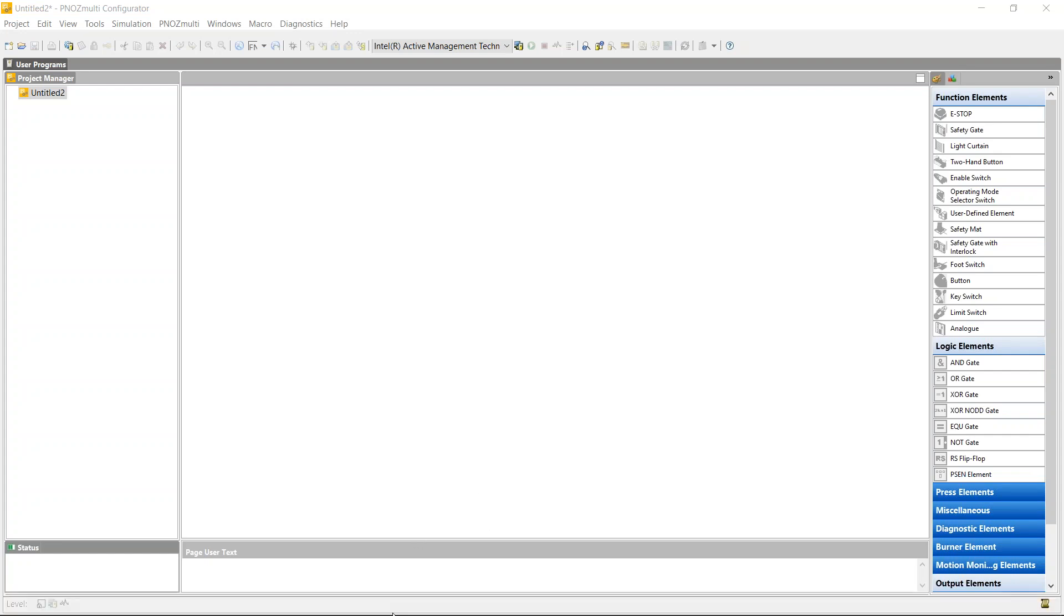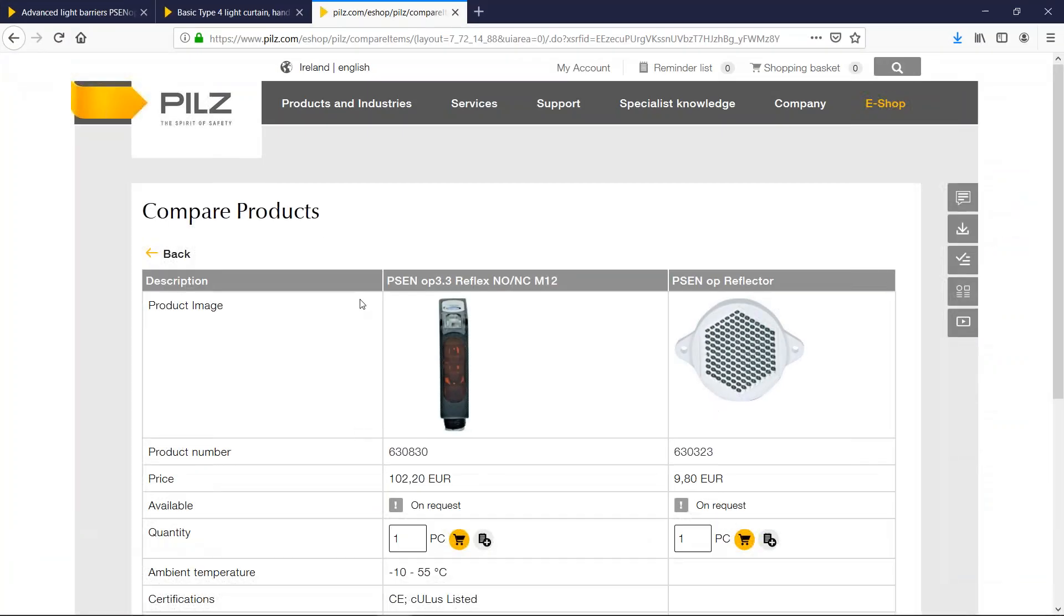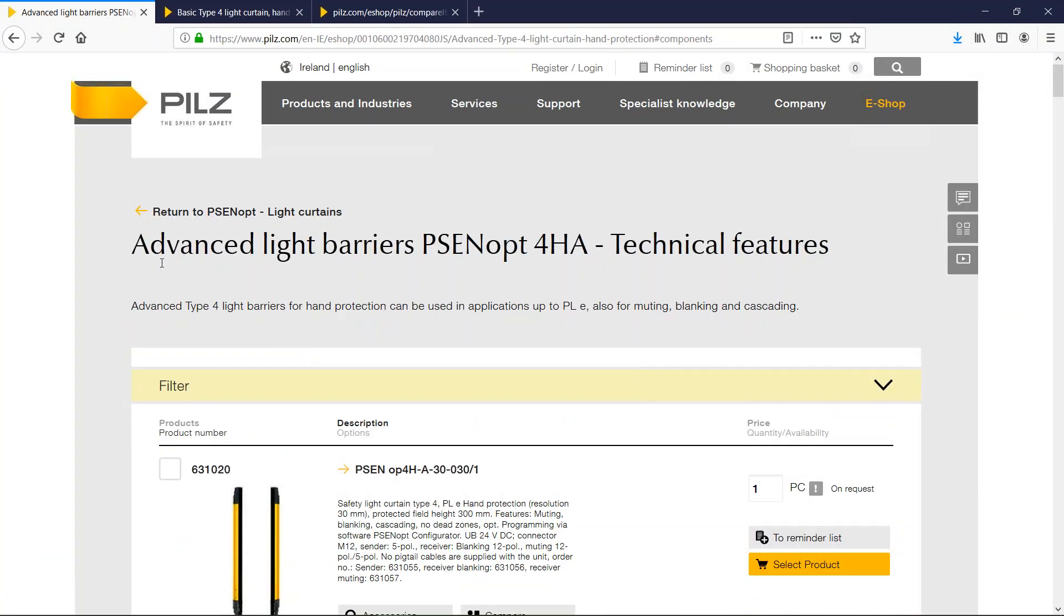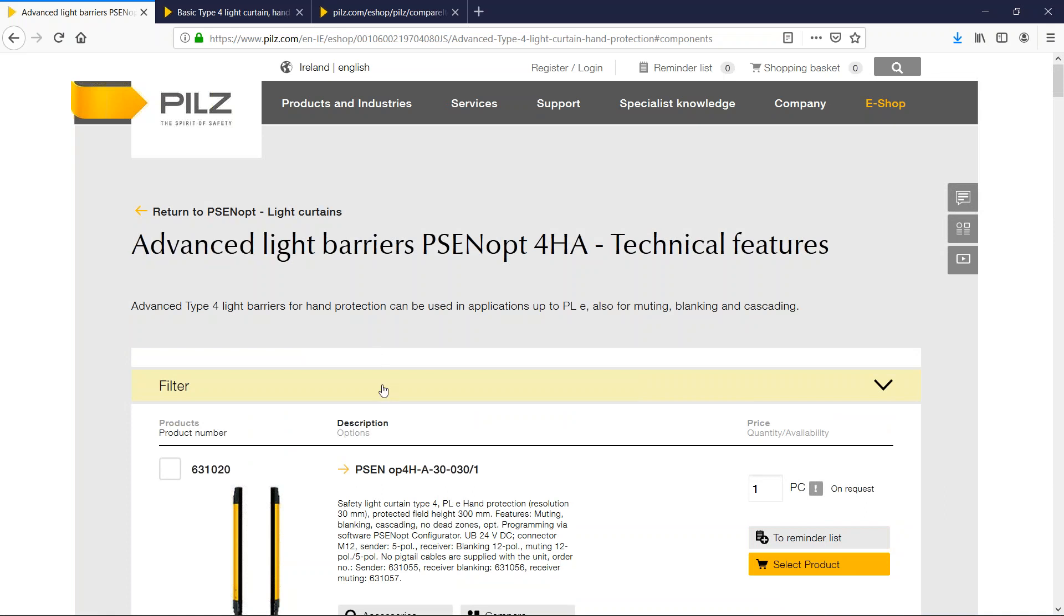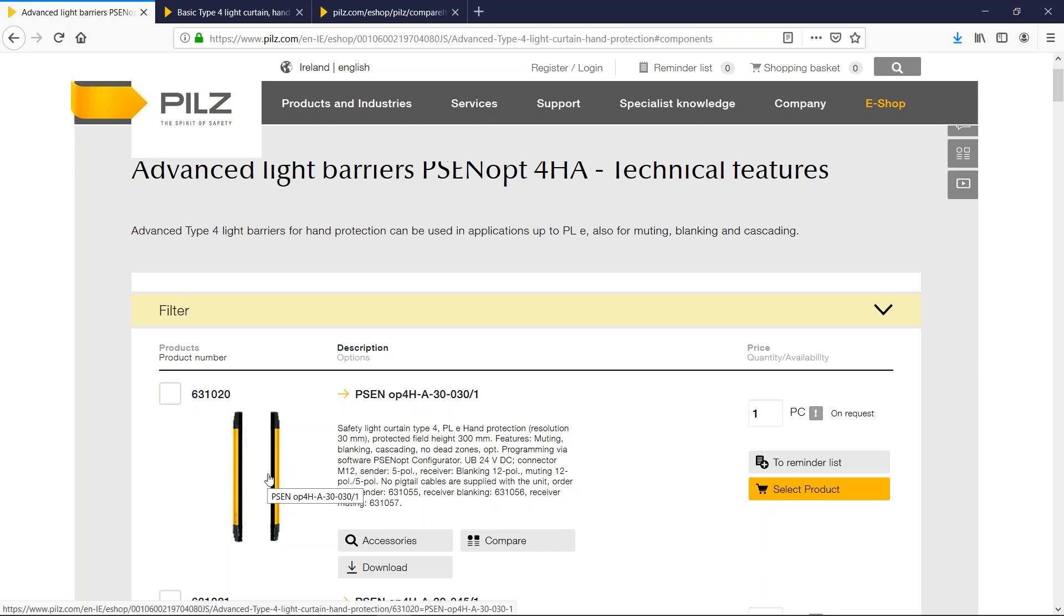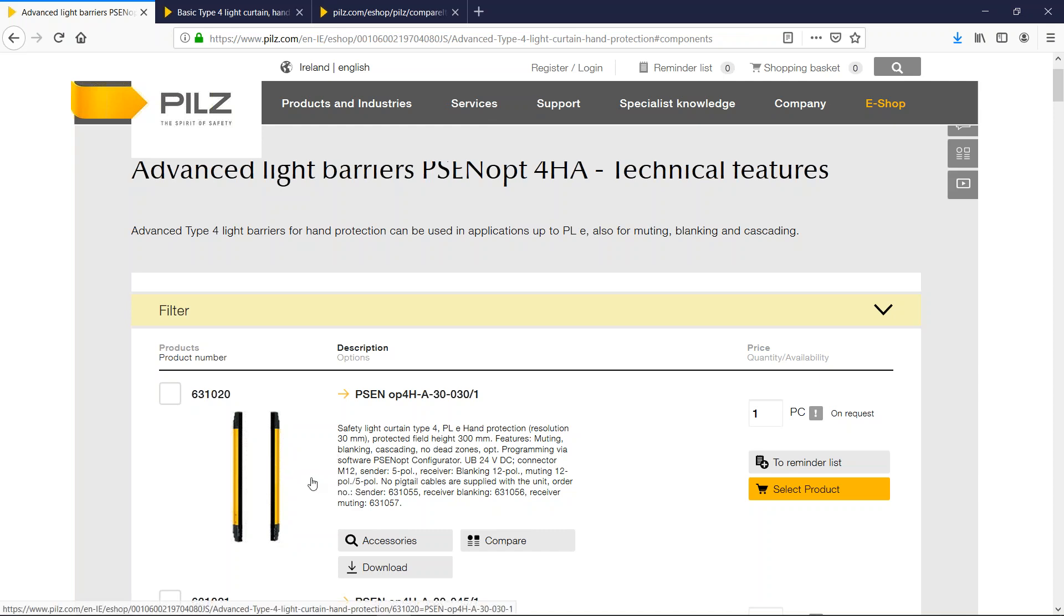Generally there are two types of ways of muting a light curtain. The first way is to buy advanced light curtains. These advanced light curtains come with the muting function and other functions like blanking and cascading built into the light curtain, so you'd also use your muting sensors wired back to the light curtain and use the logic inside the light curtain to control the muting function. So when the signal from the light curtain is received by the controller, the muting function is already taken care of by the light curtain.